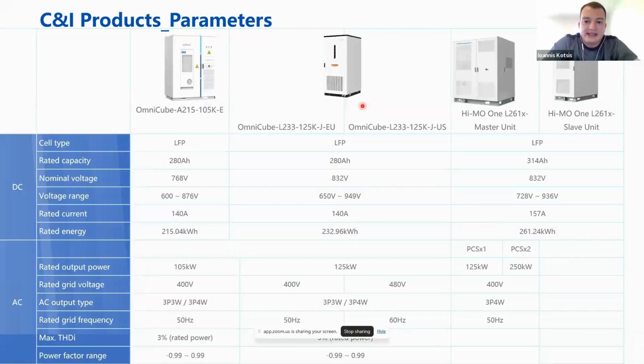Here we can see some technical data. I will emphasize the 261. Of course, LFP technology battery cells, 314 amp hours, and 261 kilowatt hours. You can see here the master unit with the two doors and the slave unit. On the master unit, we can have either one PCS of 125, or two PCS of 250, depending on the customer's needs. We can have only the master unit, or add the slave unit to increase the capacity. If we want to add the second PCS, to go to 250 kilowatts, then it's obligatory to add at least one slave unit. The slave unit is also 261 kilowatt hours. It's the same.